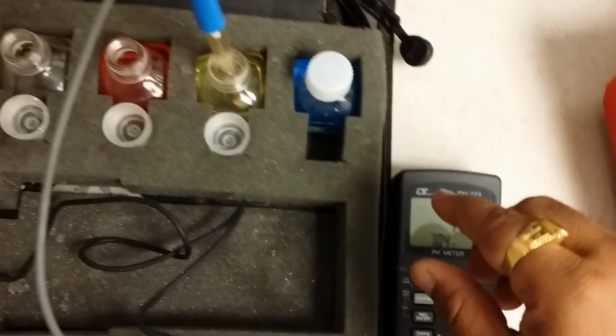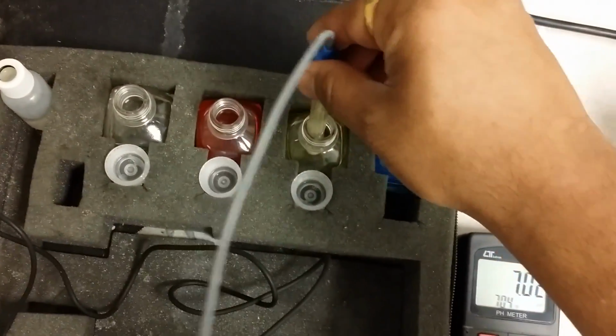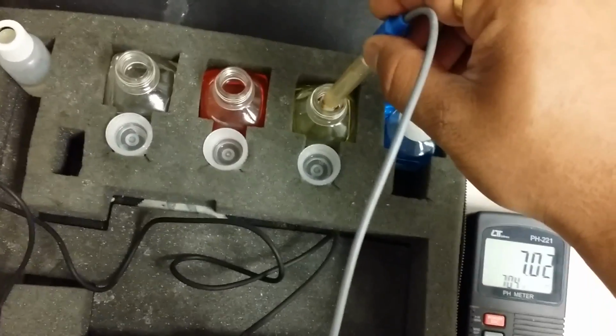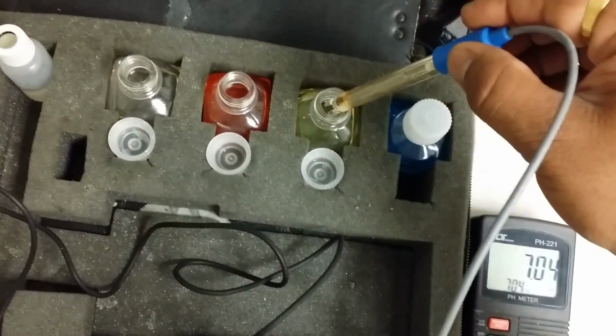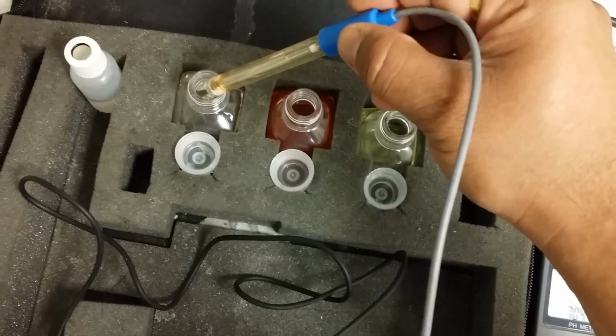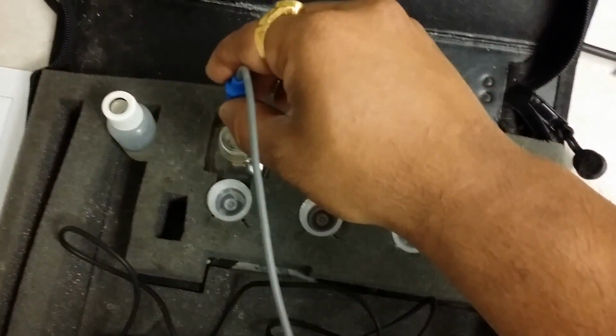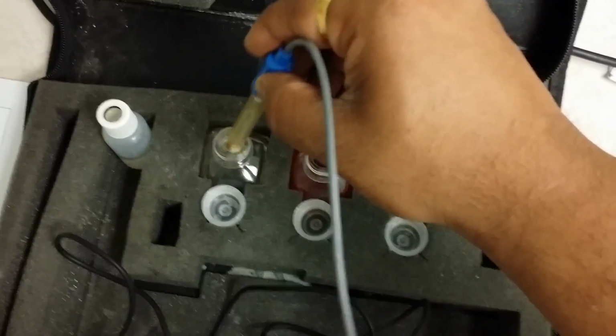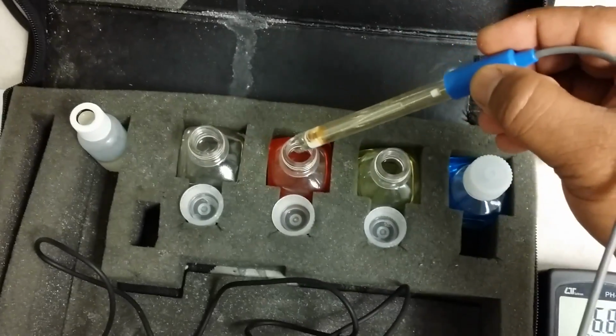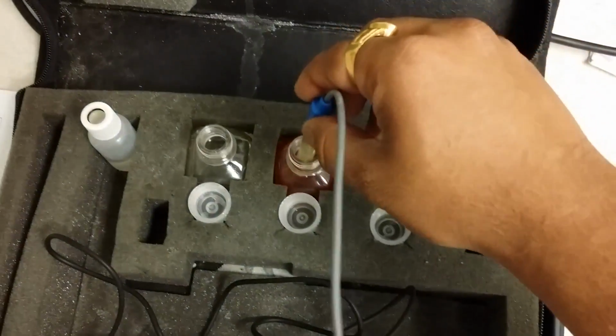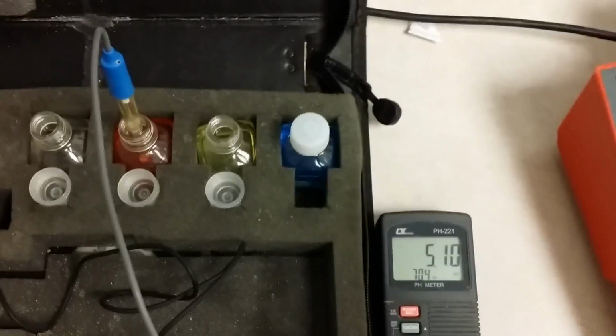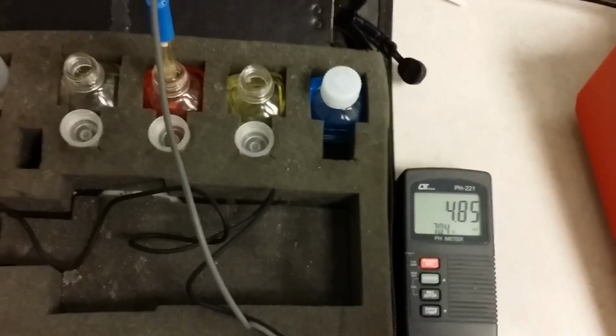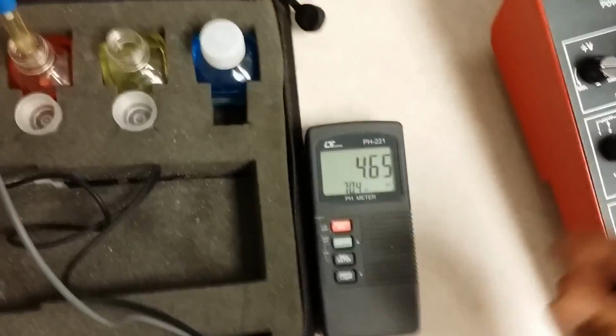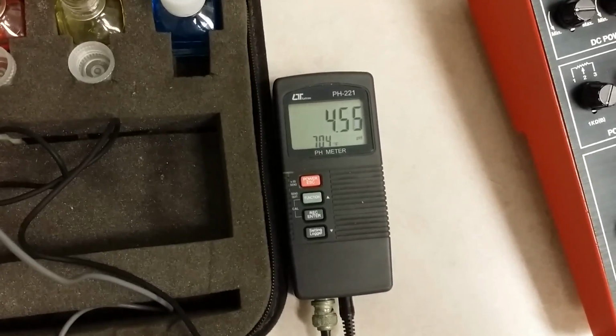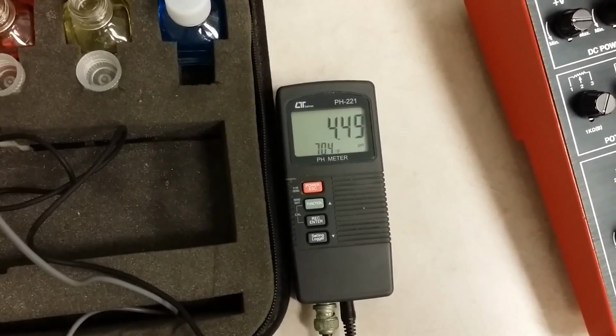Now we'll take this and clean it out in distilled water, and put it in pH 4 to calibrate, to perform a 2-point calibration. So pH 7 first and then pH 4. So right now it's reading 4 point. It's trying to stabilize.